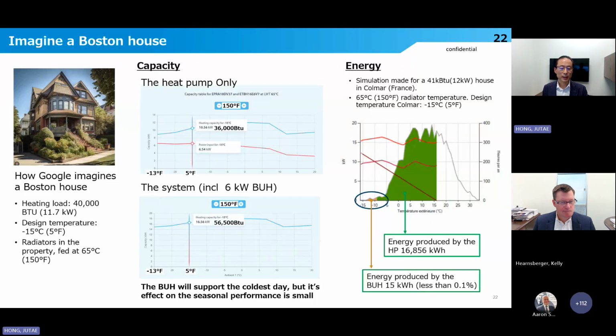Energy simulation tells us that for a 41,000 BTU house with 150 radiator in France, where design temperature is 5 degrees, most of the energy will be produced by heat pump only. And energy produced by the booster heater will be less than 0.1%. We will check this number from our field data in Maine later in this presentation.